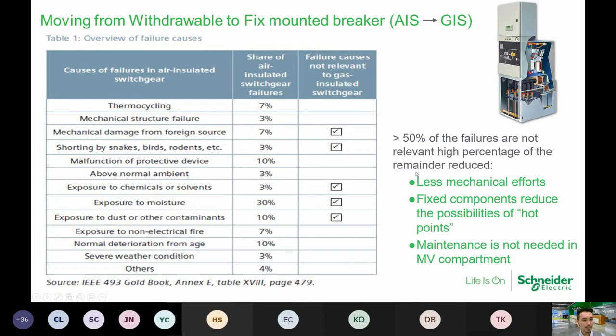Right, so by having the components housed inside the sealed SF6 gas, it is not possible for them to be exposed to external influence like dust and moisture and all these things. Additionally, you can see it has less mechanical effort for the gas insulated switchgear. Also, you have fixed components, all right, so minimizing the possibilities of hotspots. Okay, and also maintenance is not needed in the MV compartment. Okay, so we go on next.